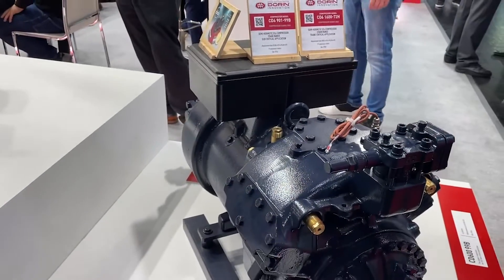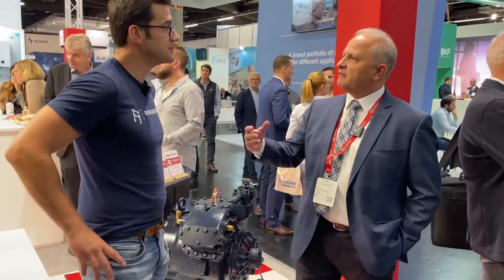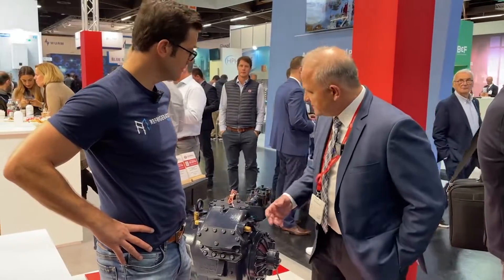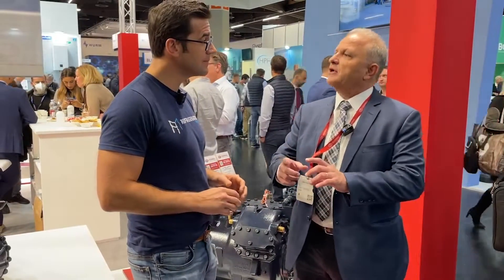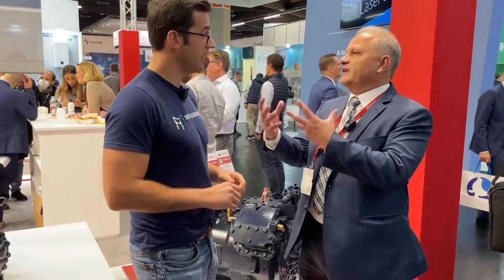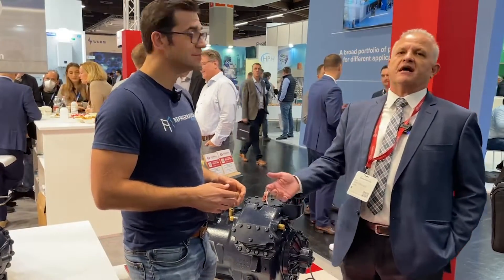Another very interesting characteristic is the oil pump. Dorin introduces a seal that keeps the oil inside this part, not touching the rotor. When oil touches the rotor, the oil becomes more fluid and pulverized. This way, we keep more oil inside the compressor — we measure 80% less oil coming out to the system.